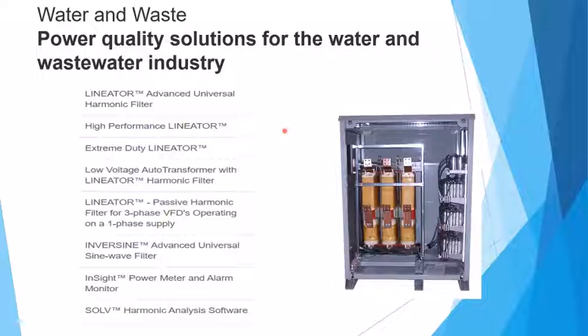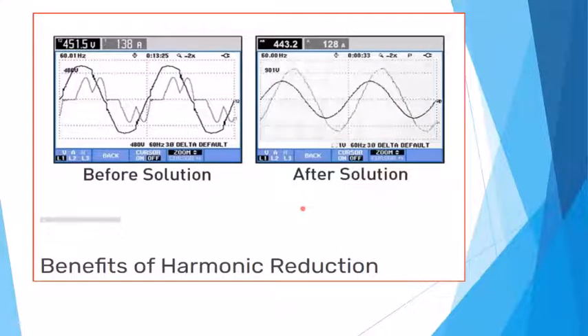drawing less true RMS amperage that you would see on an amp meter. True kilowatts was all based on how much torque we are getting out of the rotor and power. So then they've gotten to where they had the harmonic filter on the front, harmonic filter on the back, and you add additional losses in the circuit when you do that, because you've got resistance and load in between it and the power source. And so the actual power produced to the motor drops. So some of these will be 3% inductance on the front, put 3 to 5% inductance on the back, plus you've got the VFD losses, plus you've got the line reactor and the capacitor losses. So pretty soon, you've got to be really careful of what is the power source.